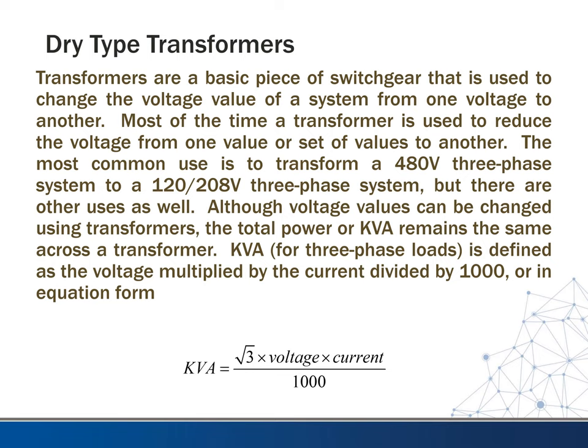So let's talk about dry type transformers. As we've talked about briefly, transformers are a basic piece of switchgear that is used to change the voltage value of a system from one voltage to another. Most of the time, a transformer is used to reduce the voltage from one value or set of values to another. The most common use is when we transform a 480 volt three-phase system to a 120/208 volt three-phase system. But there are other uses as well.